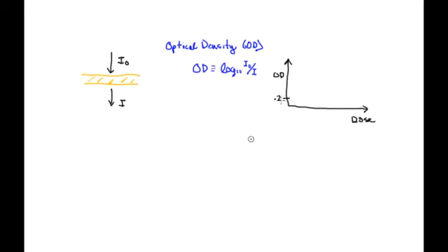It might start here at 0.2. That might be a typical value. If you have zero dose, there's some baseline fog level, and then it comes up and it saturates. It might saturate at an OD of 1. That saturation depends on the speed of the film and so on. Oh, by the way, you usually plot the logarithm of dose here. This is the very typical curve. It's called the H&D curve, for Hurter and Driffield, who characterized this in the late 1800s.